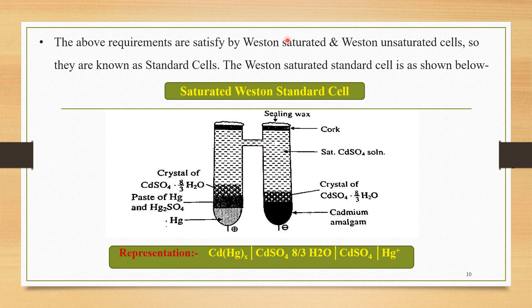The second important type of the standard cell is the Weston unsaturated cell. If we compare the saturated Weston standard cell with the Weston unsaturated cell, both cells are exactly similar. The only difference is that in the Weston unsaturated cell, there is an absence of crystals of cadmium sulphate (8/3 H₂O).